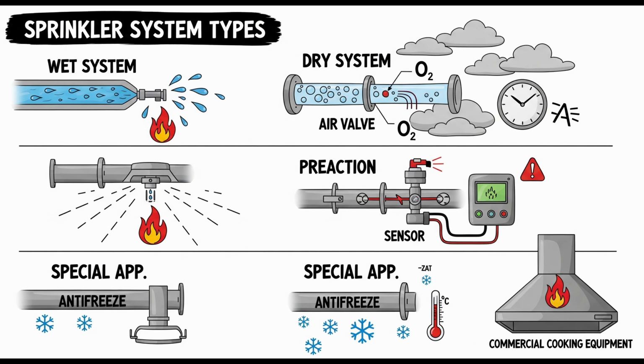Correct. NFPA 13 clarifies this interaction. It notes that hoods containing listed fire extinguishing systems are considered protected areas. They don't count as obstructions to the general overhead room sprinklers, and you don't need specific floor coverage from the overhead sprinklers underneath these protected hoods. Furthermore, the cooking equipment located directly under these properly protected hoods does not require additional dedicated protection from the general building overhead sprinkler system. That's an important clarification. It explains how the building sprinkler system, NFPA 13, interfaces with the dedicated kitchen hood suppression systems, often governed by standards like NFPA 96 and UL 300.